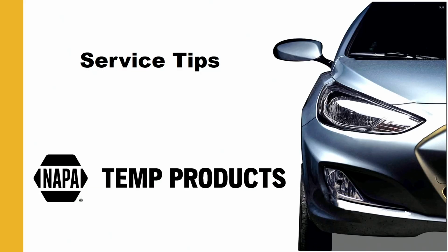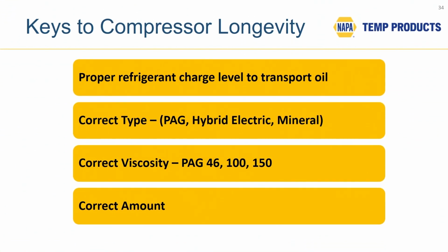Let's wrap up our session with some service tips. If you want a compressor to last, hopefully if you're replacing the original compressor, there's an expectation from you and the customer that this compressor should last the life of the vehicle. For that to happen, you need the proper refrigerant charge to transport the oil around the system. If you overcharge the system, you run the risk of slugging or liquid locking the compressor. Undercharge it, and oil's going to drop out, and now you have a lubrication issue.